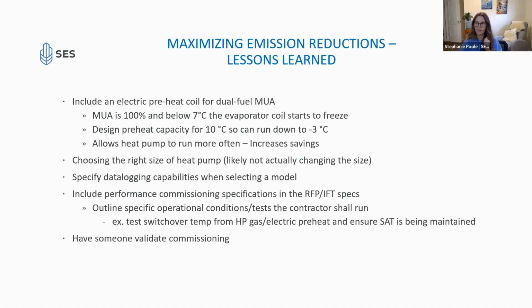Next slide. Thank you. So in general, what we typically see to maximize emissions reduction is commissioning and some sort of verification, whether it's data logging or on the BAS, some sort of way to watch the performance of this rooftop unit and make sure the compressor is coming on when it's supposed to. Because what we see in practice is that commissioning is a very loose term right now. There's a difference between performance commissioning and functional checks. Functional checks are like, yes, the compressor can turn on, check. Performance commissioning is, yes, the compressor turns on at the temperature it's supposed to, it performs properly, it's not cycling, it's turning off when it needs to. That's performance. And that's not always being done in the industry right now.